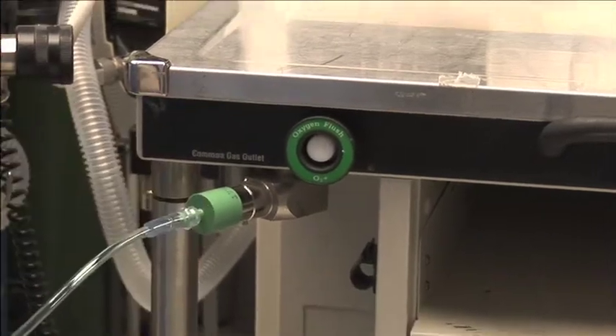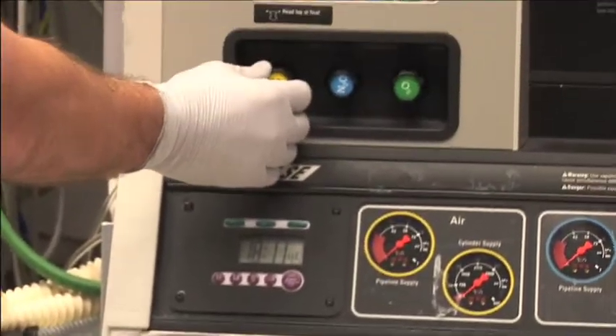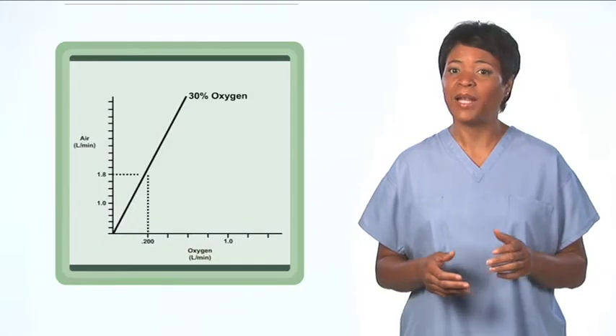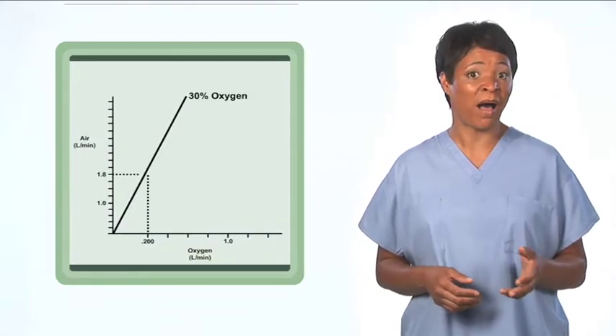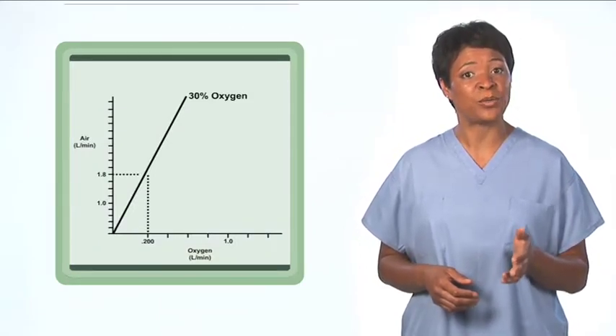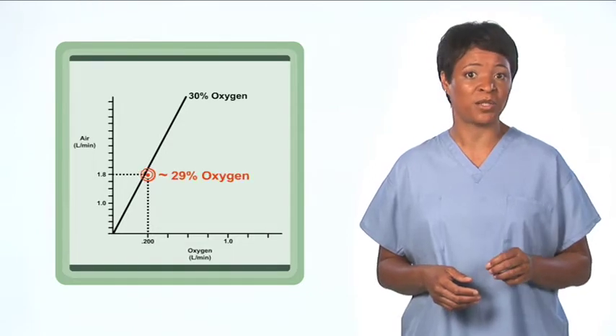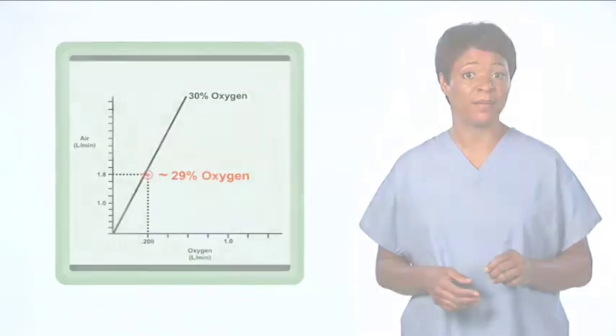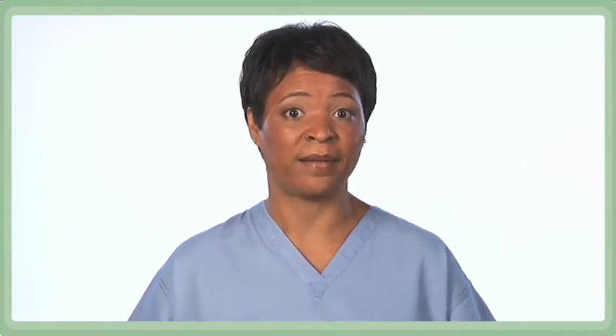Be careful about the ratio of oxygen and air used. You must remember that it takes very little oxygen added to air to enrich the oxygen concentration beyond 30%. For example, adding only 200 milliliters per minute of oxygen to 1.8 liters of air creates an oxygen concentration of 29%. However, newer anesthesia machines may not have an available common gas outlet.